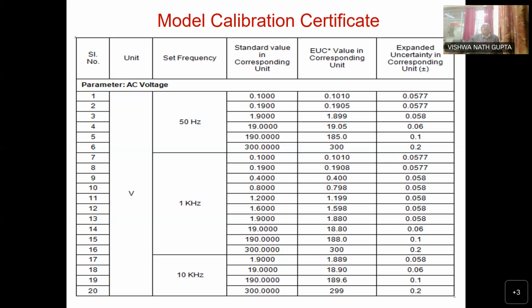Whether it is the railway line or our distribution line, in the supply line, cables are coming for testing, and overhead lines of the railway transmission line, which is purely solid copper wire, also come for testing. If we know the precision measurement, we can give the correct resistivity corrected to 20 degrees centigrade, so that our system is running very successfully. Just one example, sir. Suppose a 1 meter length of copper bar. Even if you measure it by the four terminal method, it will not fetch you the desired result, as it has very, very little resistance.